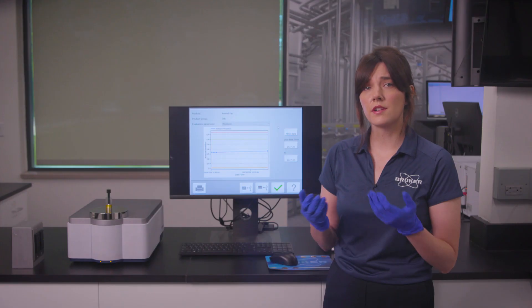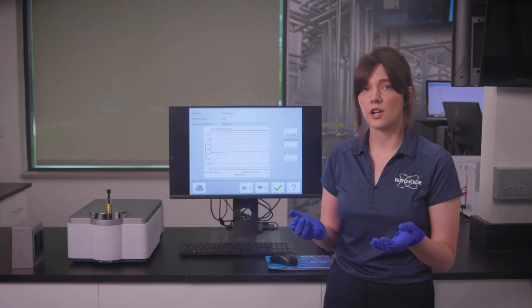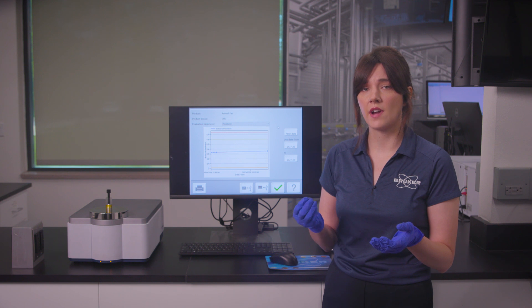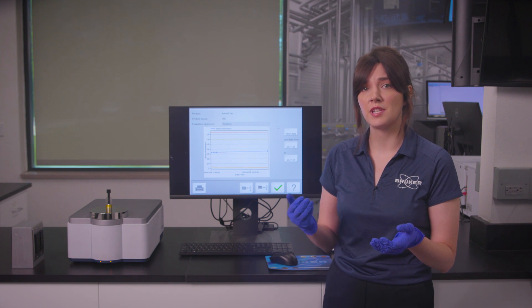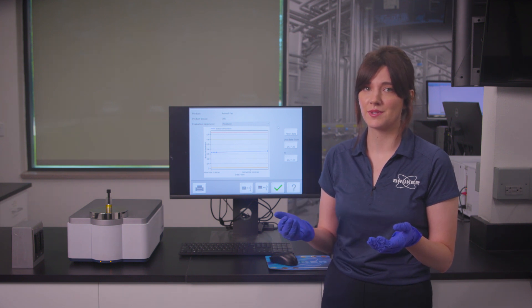For IV, you'll notice that although this value falls within the concentration range of the calibration and we're given a green check mark, this IV value is a bit on the higher end for poultry fat, so I've set limits to make those expectations and that's why it's falling within the yellow range. If it were further off or gave us a red X, this would be a sample that I may send off for wet chemistry for further analysis. We can also see from the trend chart that the Tango is providing us with great repeatability across our replicate samples.